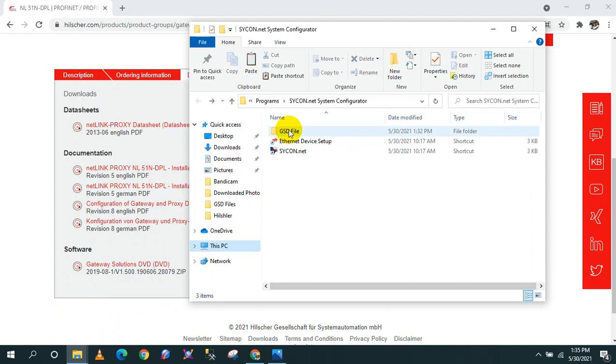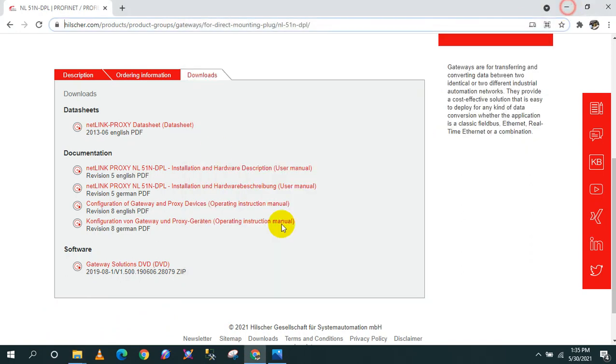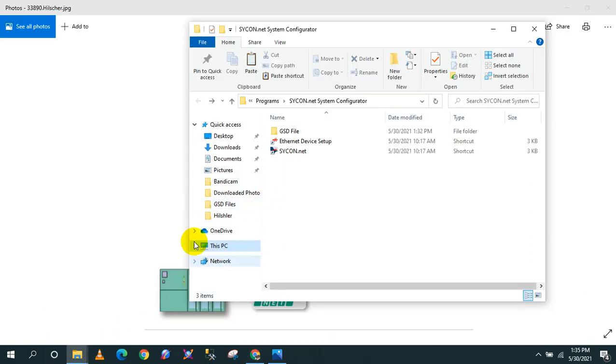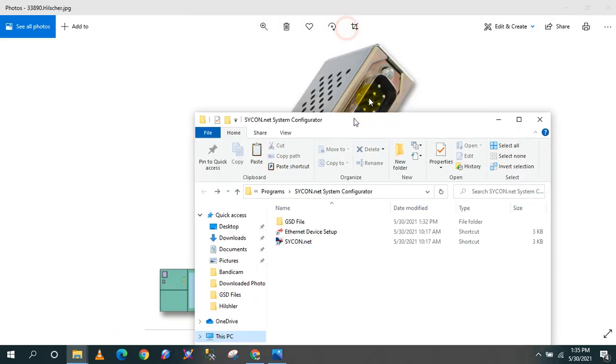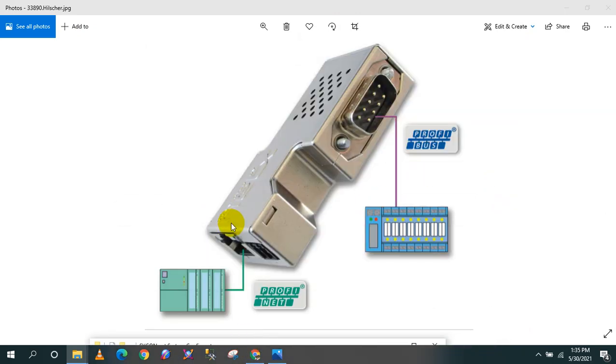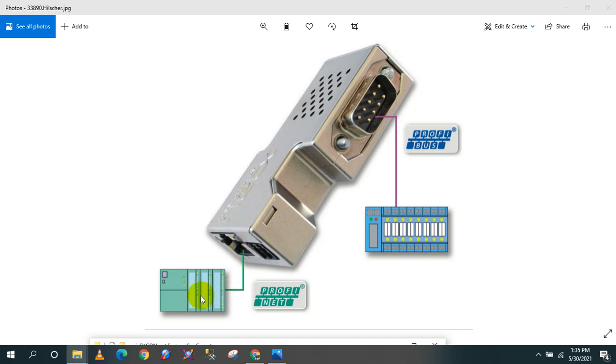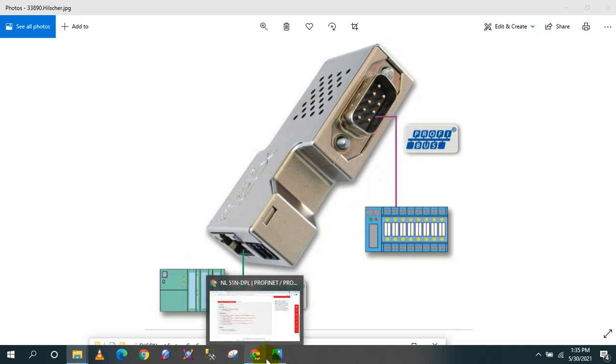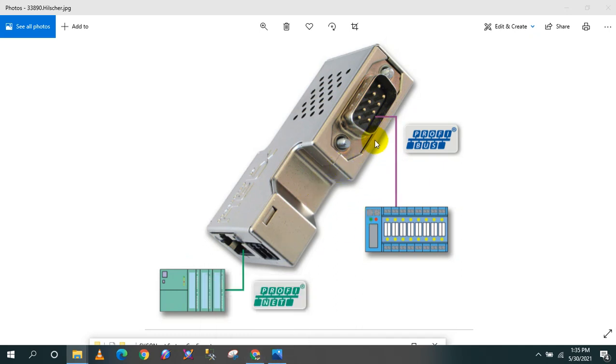Okay, let's start. Once we've already connected the device from the PLC, the LAN cable or the RJ45 should be connected to your PROFINET device, which is your Siemens PLC, and the PROFIBUS connector should be on your slave. I am using Allen Bradley slave IO module. Second, you need to open this software, Ethernet Device Setup.